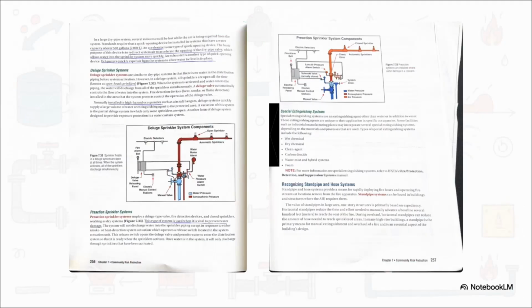But what if you're trying to protect something extreme, like an aircraft hangar filled with jet fuel? You definitely can't wait for individual little bulbs to pop one by one. You need a deluge system. In a deluge system, there's absolutely no water in the pipes. And get this, all the sprinkler heads are constantly wide open. There are 0 heat sensing elements on them. When external fire detectors sense heat, smoke, or flame, a massive deluge valve opens and water simultaneously blasts out of every single sprinkler in that entire zone.